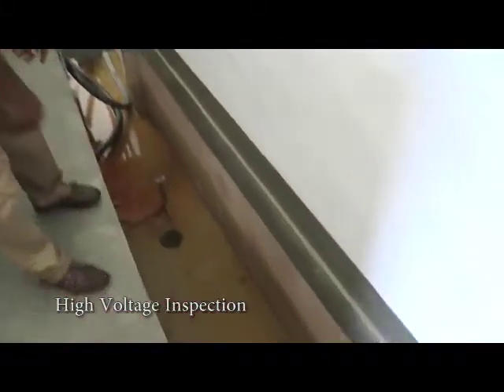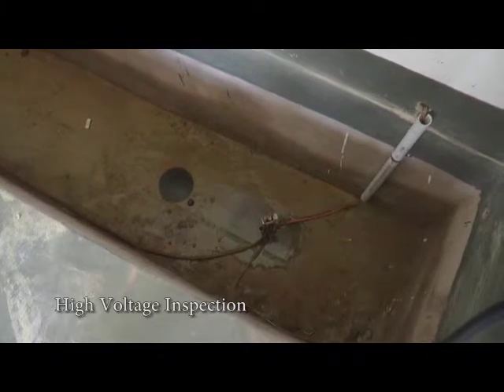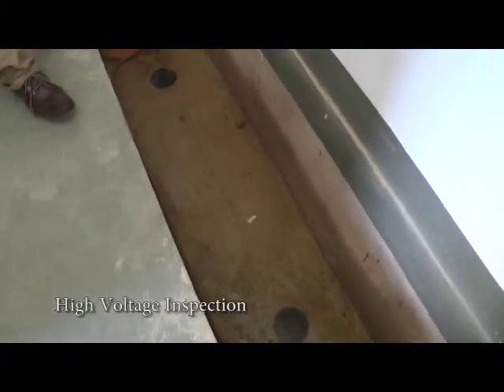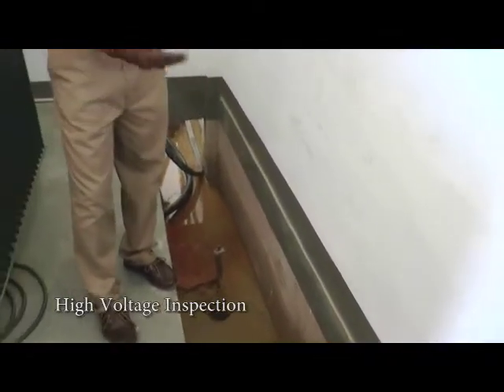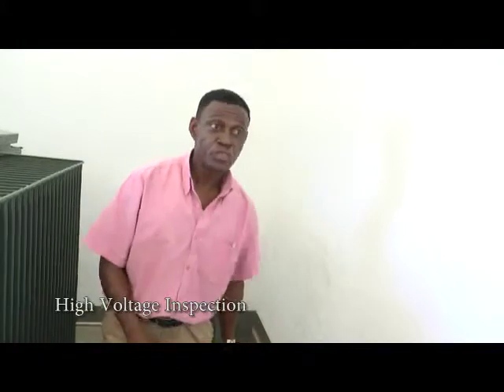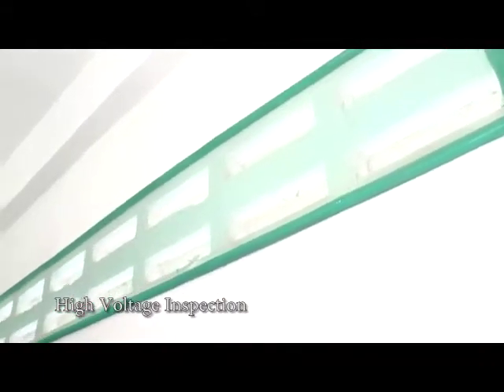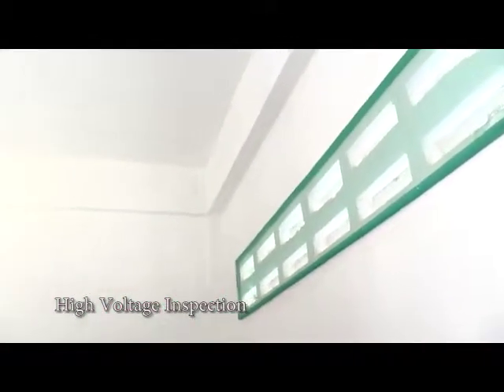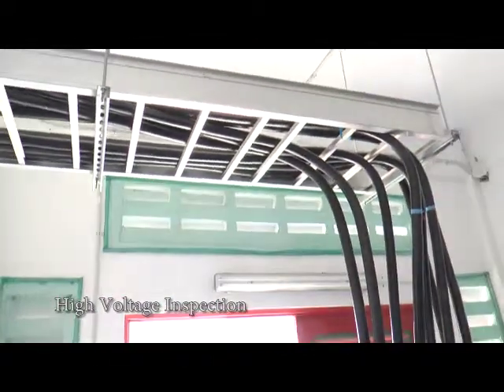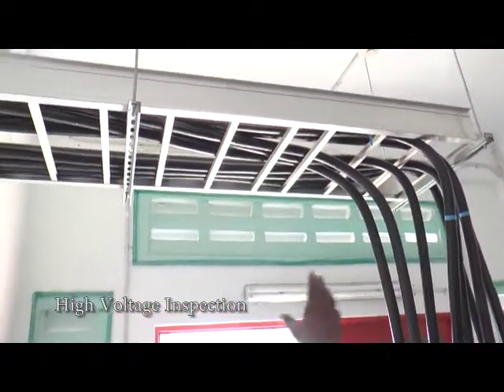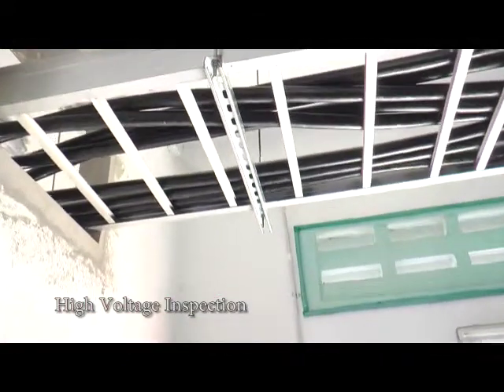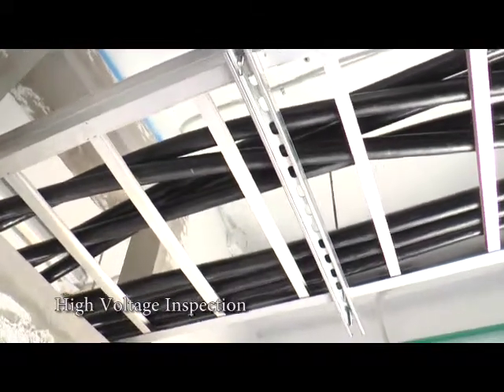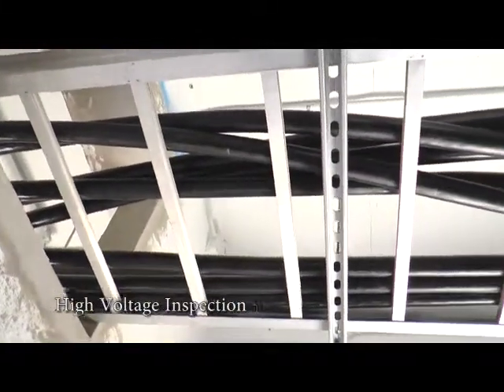The electrical inspector is to ensure that rods are driven in the four corners of the transformer room. This area is all properly done in the event that there is oil spillage or even water leakage within the system. We are also to check the entire physical aspect of the transformer room. Things like proper ventilation. This is to allow the transformer area to remain cool and not be too hot with regards to the transformer windings within the installation. We are to check the cable tray in which the cables are run to make sure that they are done in a workmanlike fashion and properly secured within the transformer room.